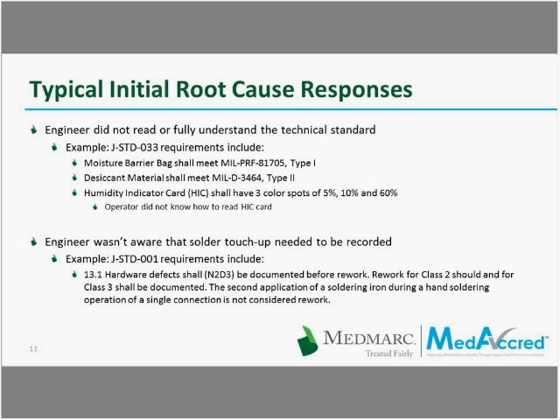That's really a good general flow-down of what the FDA calls good documentation practices, making sure everything is recorded. For companies and CMs that are only doing maybe 10 or 15% medical with the rest commercial, it's important to flow down those medical-specific requirements to make sure everything is documented effectively.